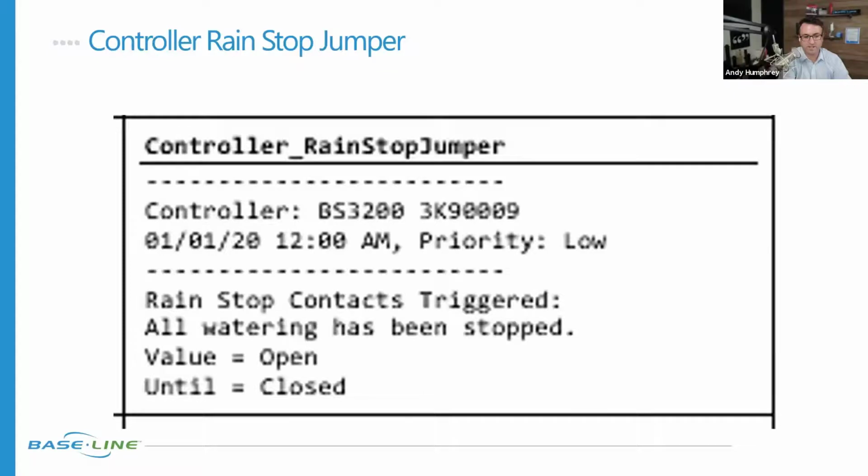Basically it's saying, hey, there's a rain event. But I don't have a rain switch. Why do I have this message? That's a good reason to call support right there. Could be the jumper, which we do see. People never pull that jumper wire off, do they?